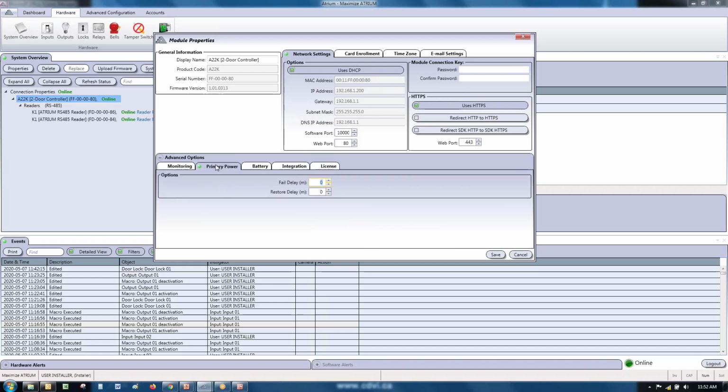In the primary power here, the tab, this is where you can, in the system, define if there's a primary power failure, I want to send an email, for example. So what is the delay that indicates that there is a power failure? Do you want to increase this? Maybe you have a back UPS. I don't know. How many minutes do you wait before the system says, once primary power has failed, wait 2 minutes before indicating that the primary power is now off?